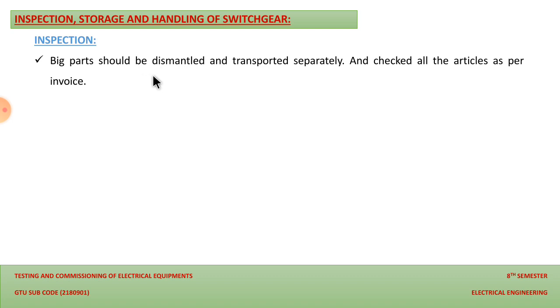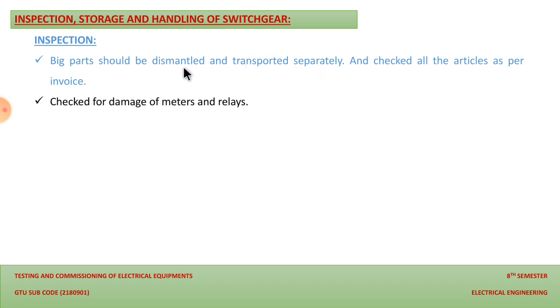Big parts should be dismantled and transported separately. This is the most important factor that we should keep in mind: the accessories which are mounted on the switchgear should be dismantled, and only then should it be transported. Otherwise there might be chances of damage during the transit of the equipment. And check all the articles as per the invoice which was sent by the vendor or manufacturer. This is the most important point while we inspect the switchgear after transit.